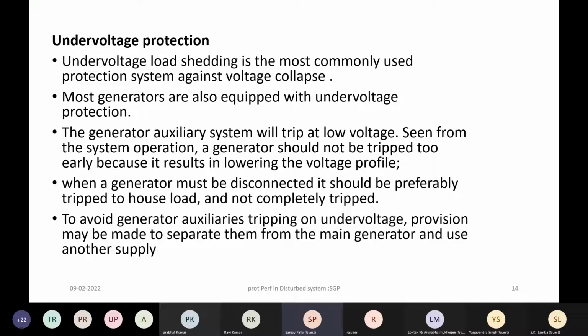Now the setting of the under voltage protection should be such that the grid disturbances and the mitigation measures in terms of special protection scheme, reactive power support interventions, and other schemes should get a chance to correct the voltage. Otherwise, if the power station trips on under voltage of the auxiliaries, then it will further aggravate the situation. So care has to be taken while setting the under voltage protection in the thermal power stations.